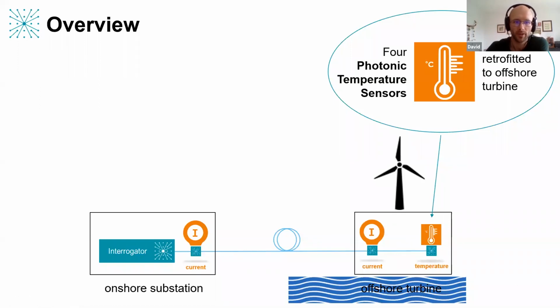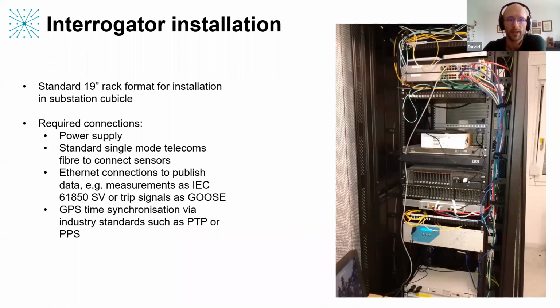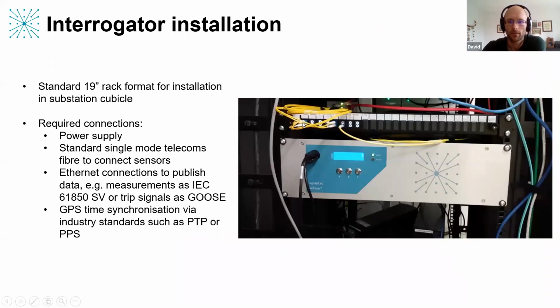Now to go into a bit more detail of each of these elements. First of all, we have the interrogator. This comes in a standard 19-inch rack to be installed in the substation in a cubicle. That needs obviously be powered. It needs a power supply. It needs a standard single mode telecoms fiber to connect to these sensors. Ethernet connections are required as well. These are to publish our data and measurements.